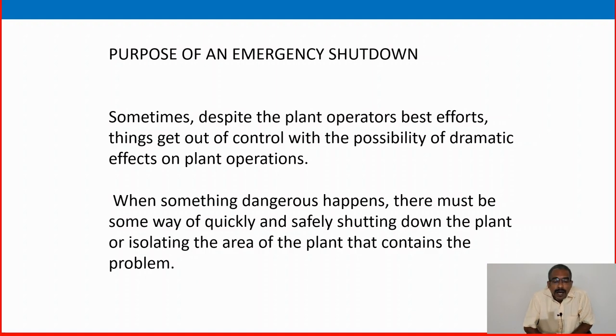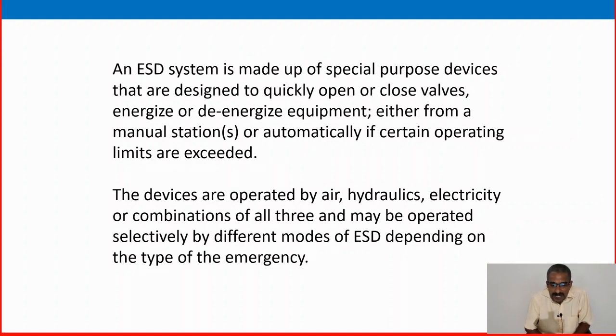Purpose of an emergency shutdown: sometimes, despite the plant operator's best effort, things get out of control with the possibility of dramatic effect on plant operation. When something dangerous happens, there must be some way of quickly and safely shutting down the plant or isolating the area that contains the problem. An ESD system is made up of special-purpose devices designed to quickly open or close valves, energize or de-energize equipment either from a manual station or automatically if certain operating limits are exceeded.